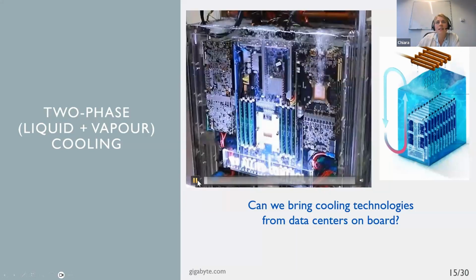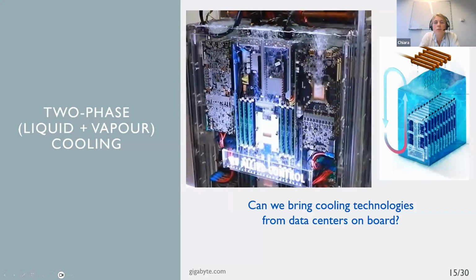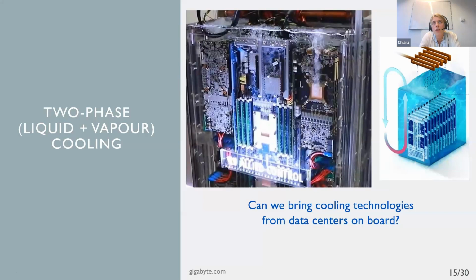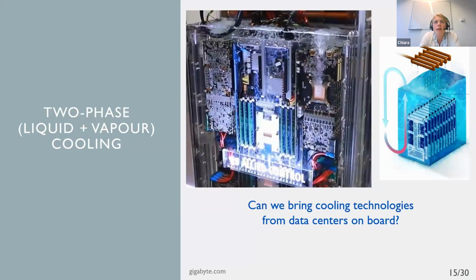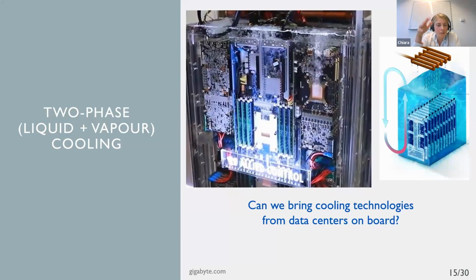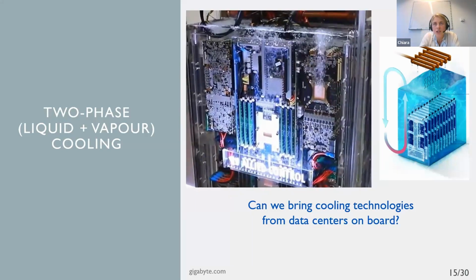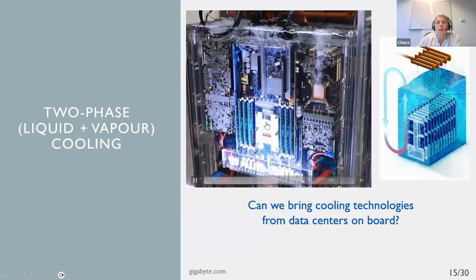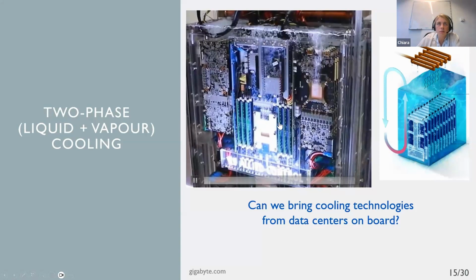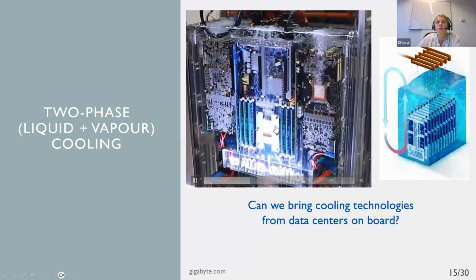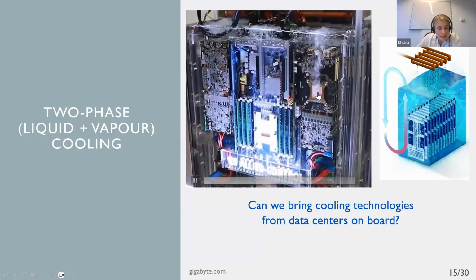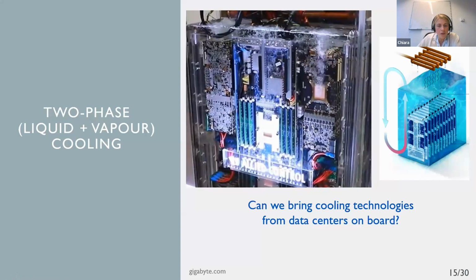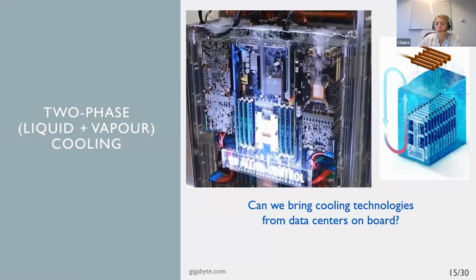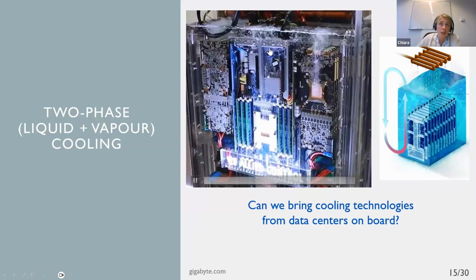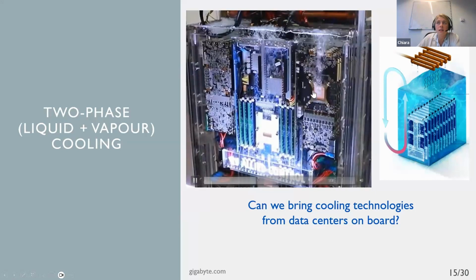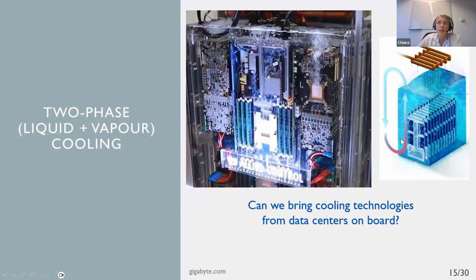Here in the video we see an example from Gigabyte of immersion cooling systems, which we're probably familiar with, where the motherboard is directly immersed in a pool of dielectric refrigerant. The liquid evaporates close to the hot spot, in this case the CPUs and GPUs of the card, and thanks to the latent heat of evaporation we can remove very high heat loads.